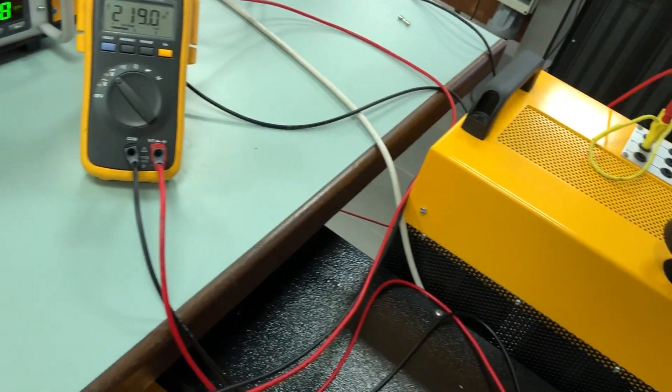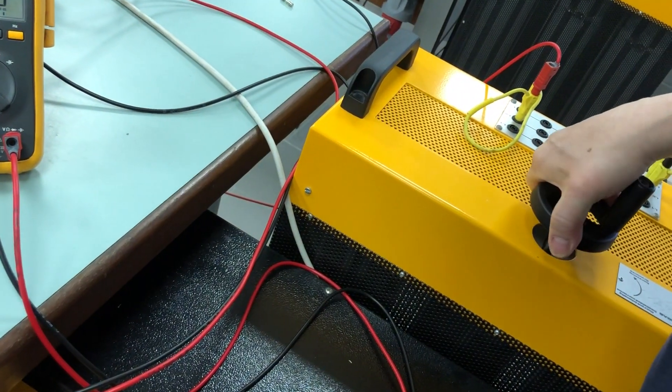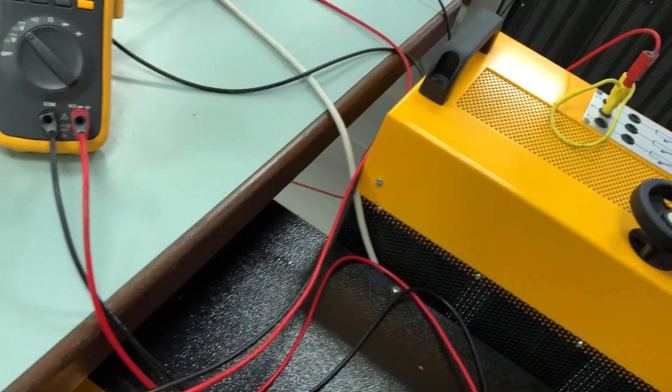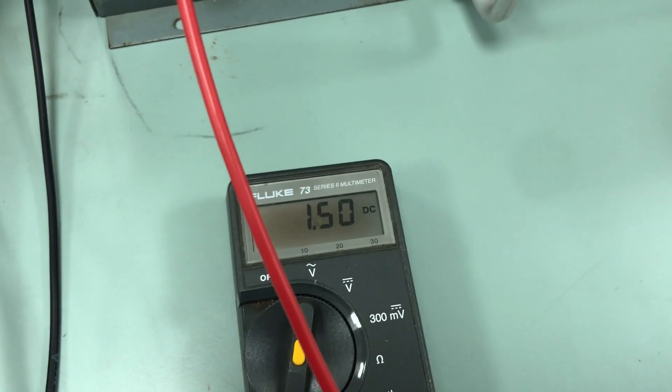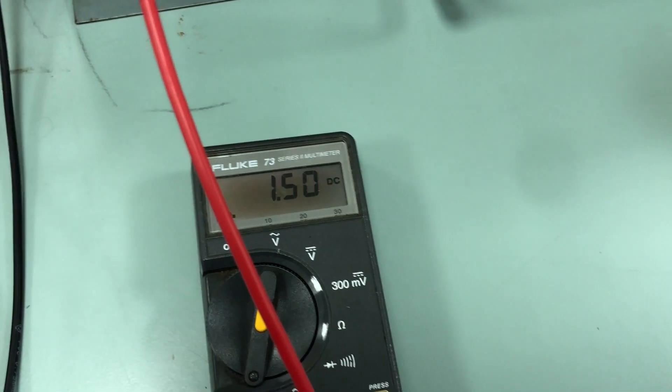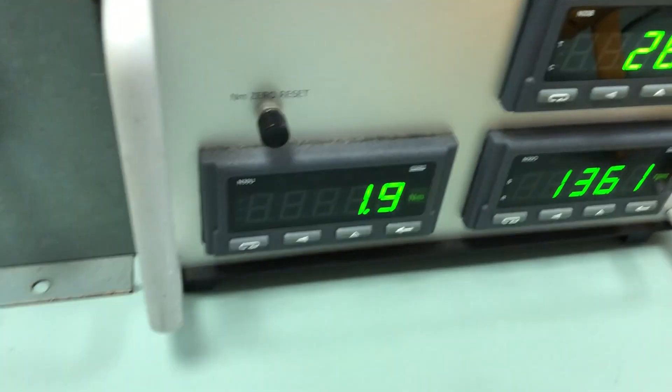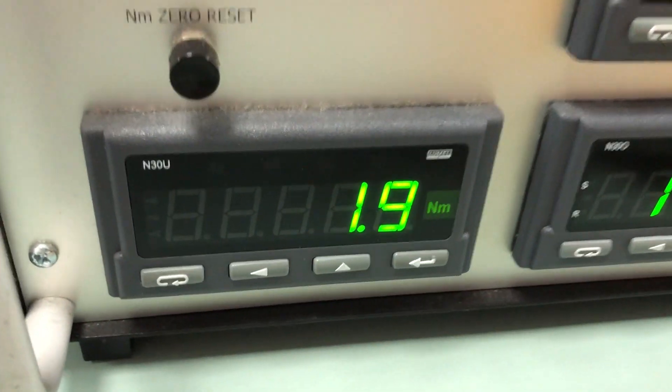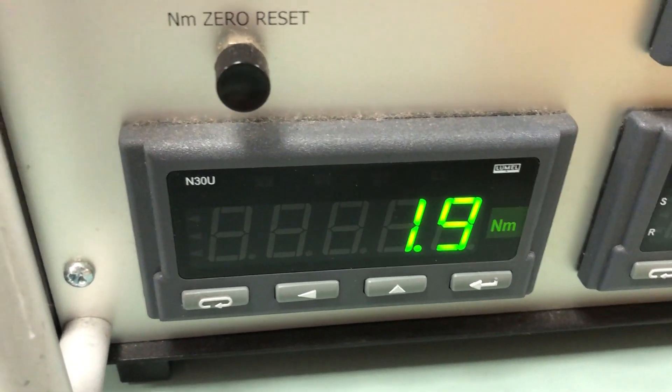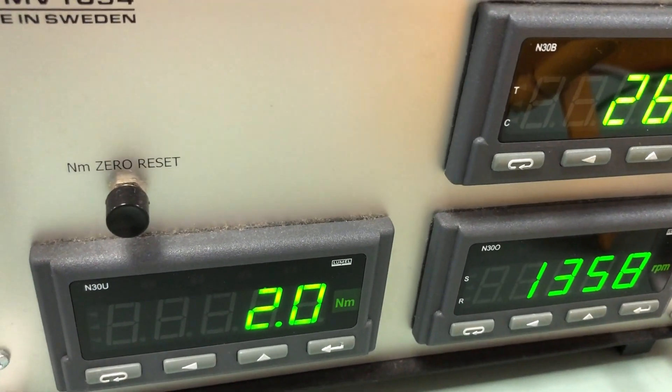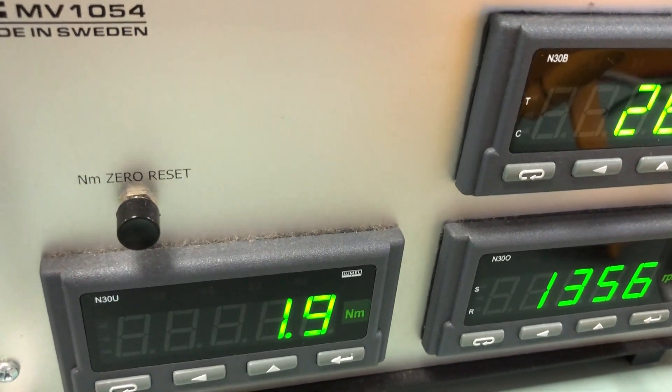Not quite there so this is when you have to increase the load via the load bank. Okay and it's done now it's 1.5. 1.5 armature current therefore take note of the speed and take note of the torque. The torque is 1.9 Newton meter. Speed is 1356.